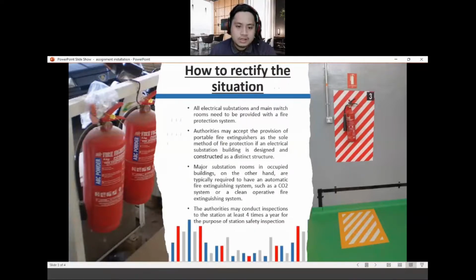First of all, the electrical substation and main switch room need to be provided with a fire protection system. Next, authorities may accept the provision of portable fire extinguishers as the sole method of fire protection if an electrical substation building is designed and constructed as a distinct structure. The third is that major substation rooms in occupied buildings, on the other hand, are typically required to have an automatic fire extinguishing system such as a CO2 system or a clean agent fire extinguisher system.